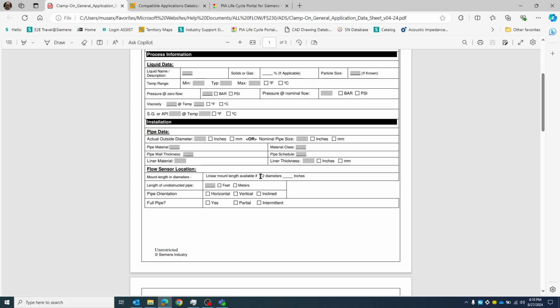Go ahead and provide for us how much straight run you have on the pipe, and if it's less than 2 diameters, give us that distance or dimension in inches so we know that we have enough room to mount the mounting hardware onto the pipe or not. That's also echoed here with the length of unobstructed pipe, either in feet or meters.